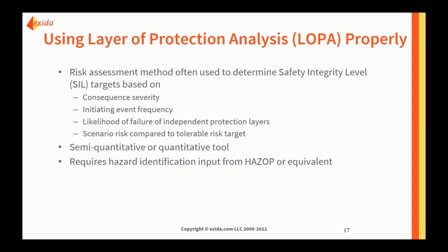You can look at it in a semi-quantitative way, where each protection layer is an order of magnitude or nothing. Or we can look at it in a more quantitative form, where each protection layer does indeed have an estimated probability of failure in preventing the accident.